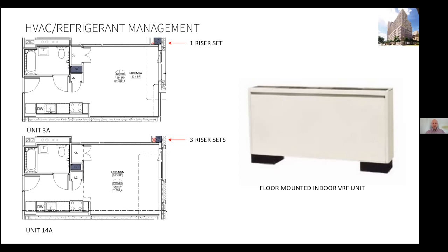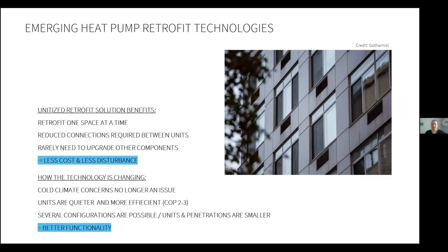The other change in this building is the floor-mounted indoor VRF unit, which was selected by the development team as an aesthetic because they felt it had a more residential feel, similar to a PTAC, but smaller. We also wanted to mention, although we are not using them on BOE projects, but other high-performing projects in our office, that there are a few unitized heat pump package terminal units that are coming to our market. A unitized option means there are no refrigerant lines running throughout the building between the apartment evaporators and the condensers on the roof. This means lower construction costs and lower carbon impacts.